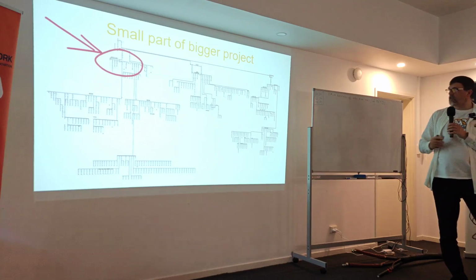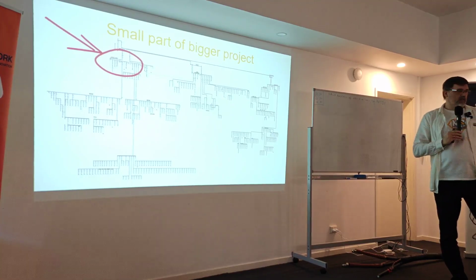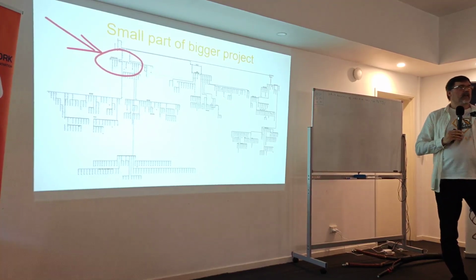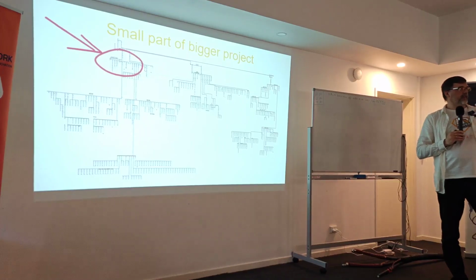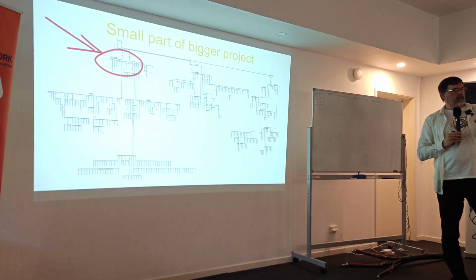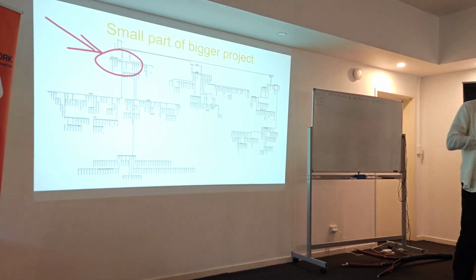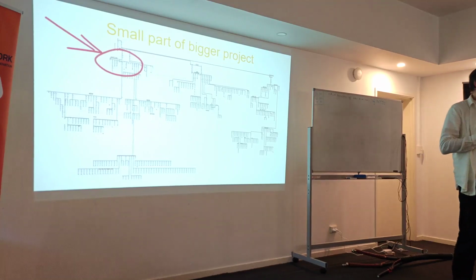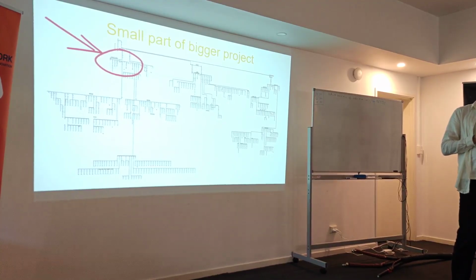Okay, we go to one station and I see it's not 1 or 2 transformers, or one is gone or something else. And I have seen that people tend to have this belief that we have documentation. And we always welcome it when the documentation is available, so I keep asking for it. So when they send it, we look at it, we prepare, we go to site, and then we start to go through it. And a fun thing is, what I do, I just have a list, left and right, that we check on what's in the switchgear. Let's say 25 feeders plus incomer. So I have to find 25 feeders, and the incomer I see.